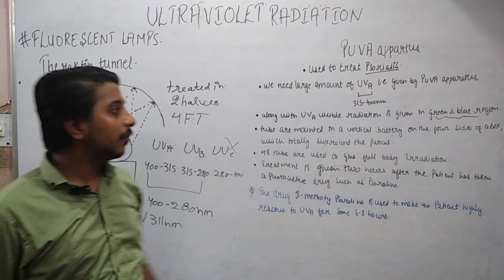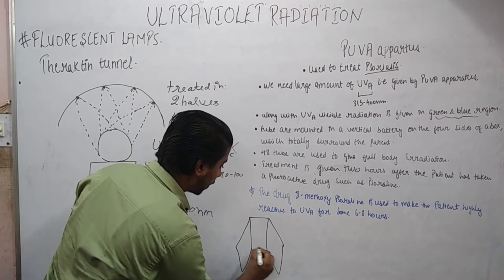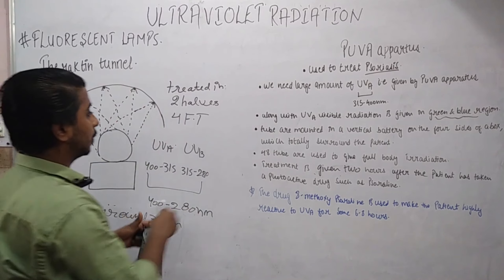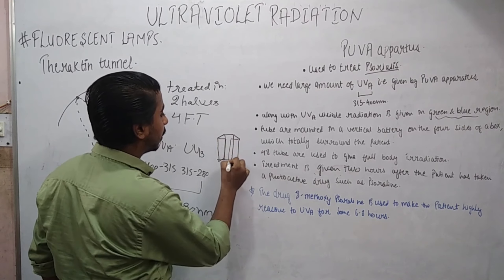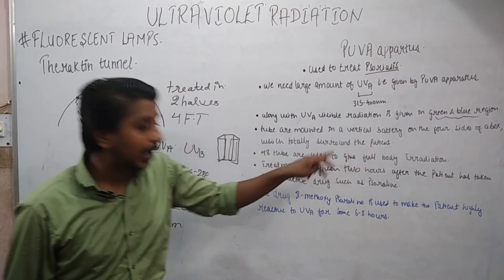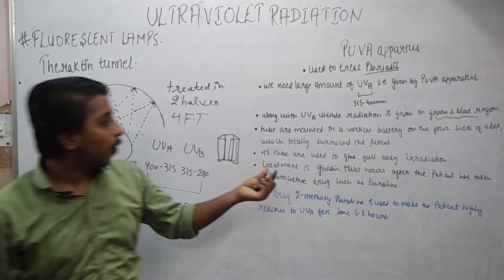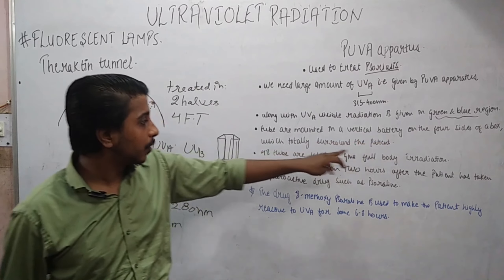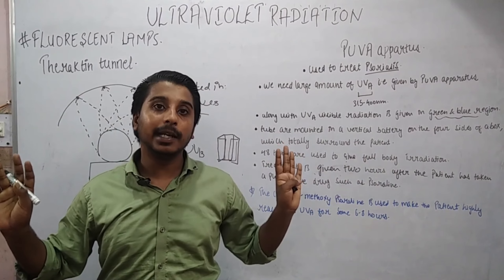The tubes are mounted in a vertical battery on the four sides of the box. There are four sides to the box — front, second, third, and the back side is the fourth — and 48 fluorescent tubes in total are used, mounted around the patient, to fully irradiate the whole body in a single attempt.